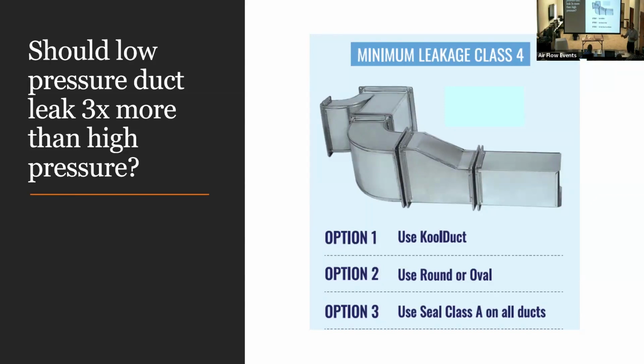So it's going to require engineer's intervention. Option 2, round, is leakage class 2. Like good spiral ductwork is only leakage class 2. Finally, you can use Koolduct on the low, like do whatever you want on the high pressure side. On the low pressure side, you can use Koolduct because it's always leakage class 3.